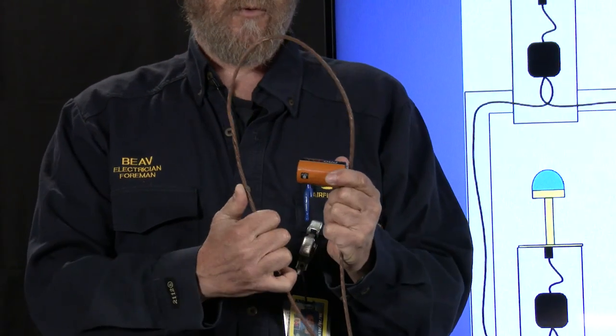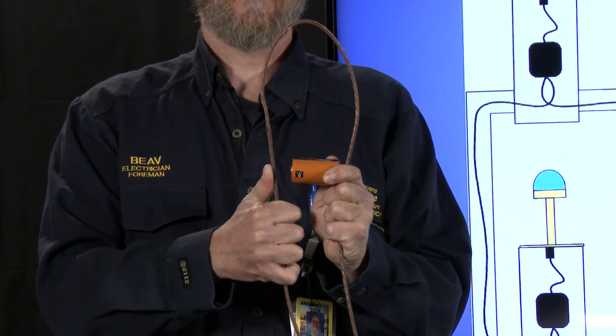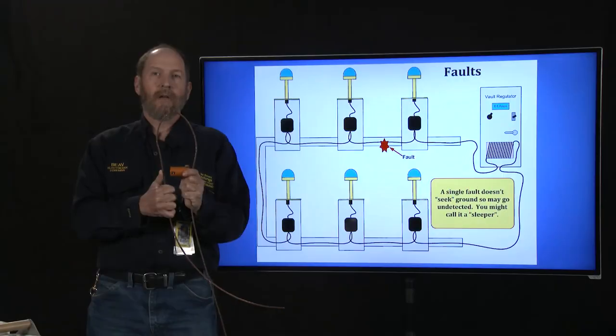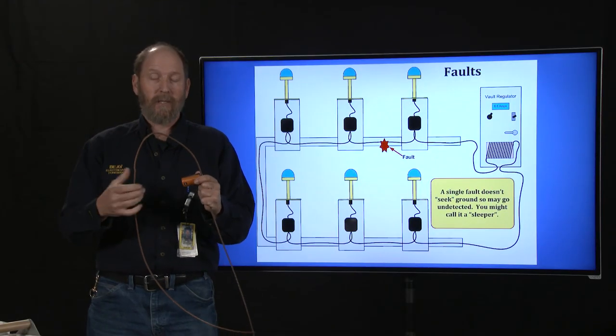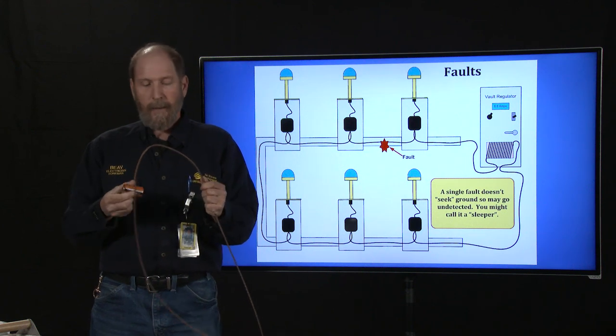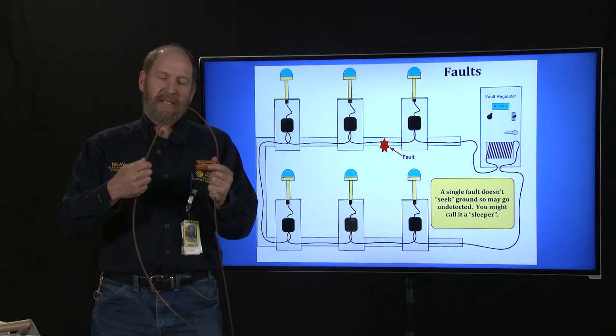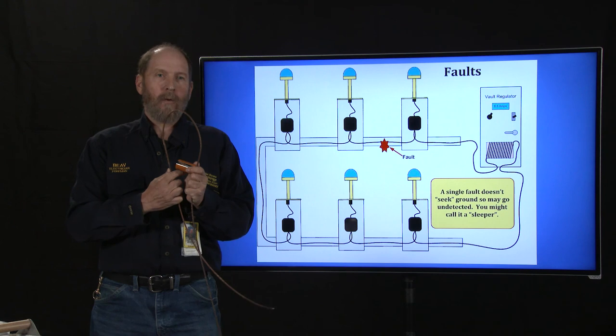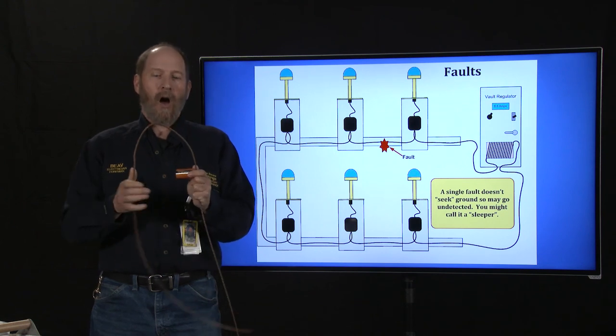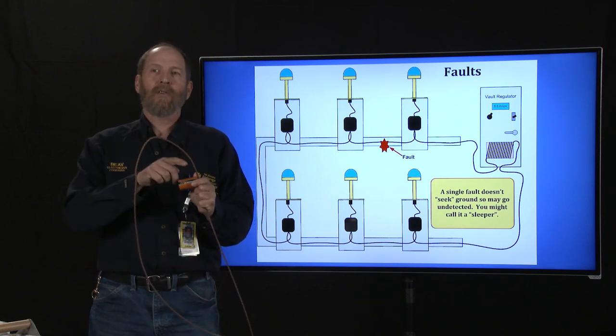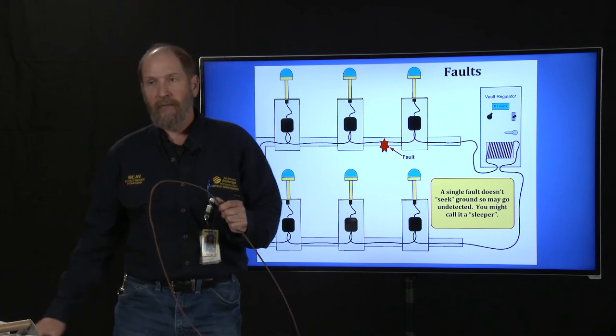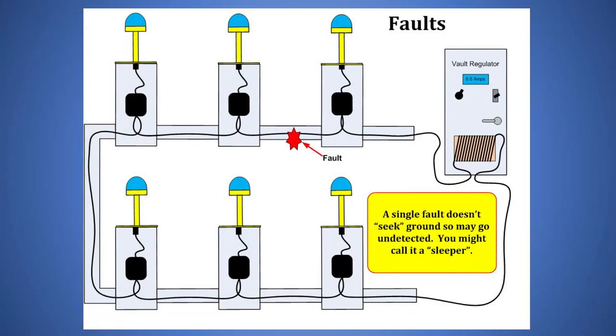So what would happen if I had my battery connected to this wire and I brought this part of the wire, the ground wire, down and touched it to the battery? Would it discharge? Yes, it would absolutely, completely discharge to that wire. So it's not discharging to ground, it's discharging on the ground wire to itself. And that's what happens in our constant current system. So if a single fault doesn't go anywhere, we could call it a sleeper.